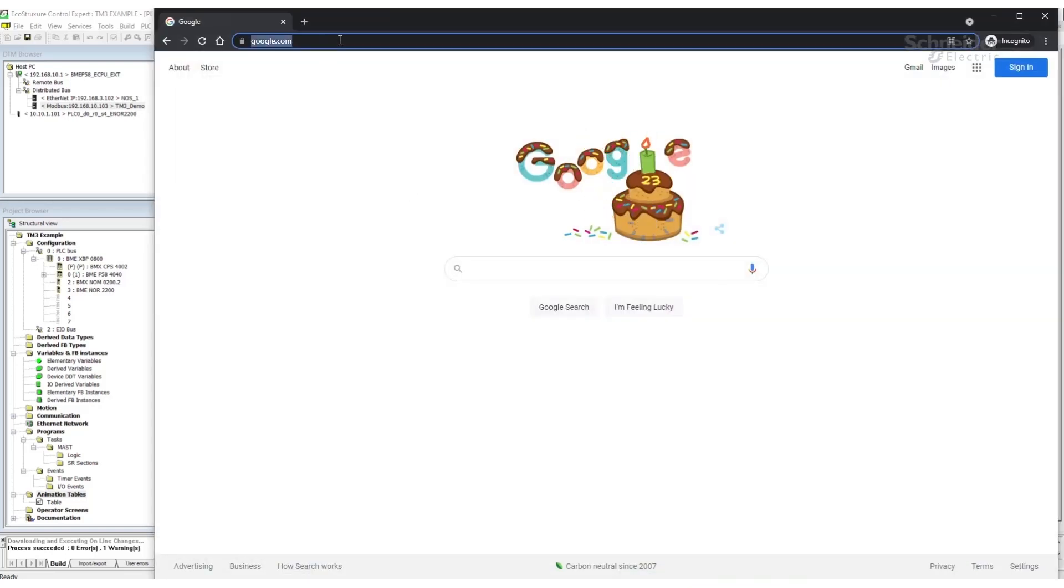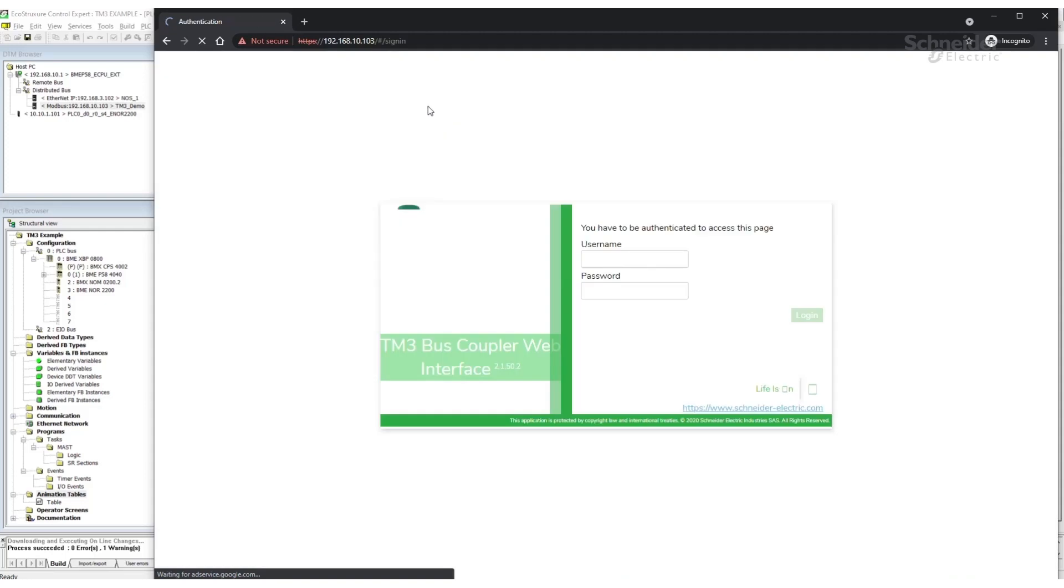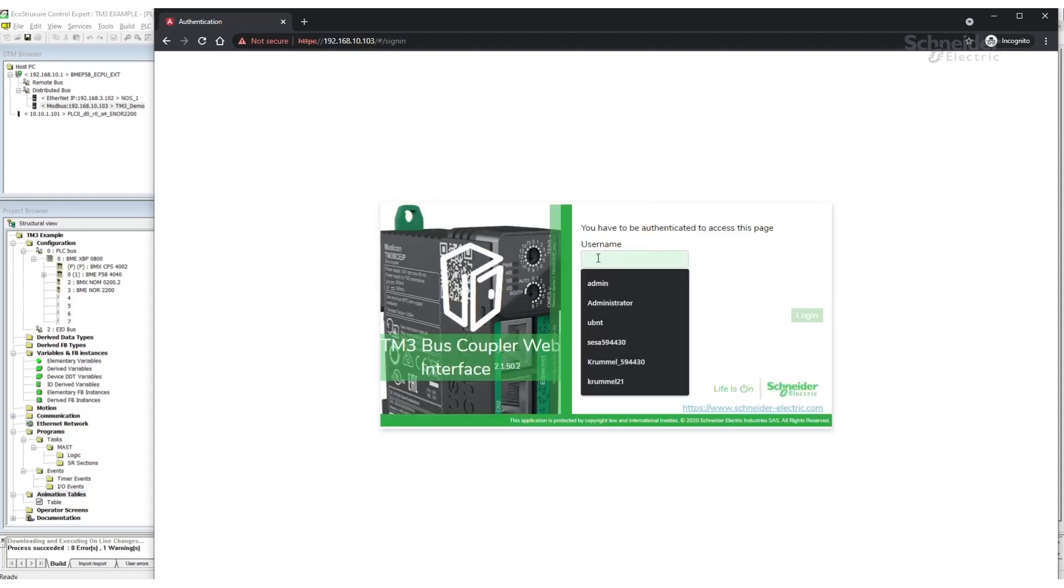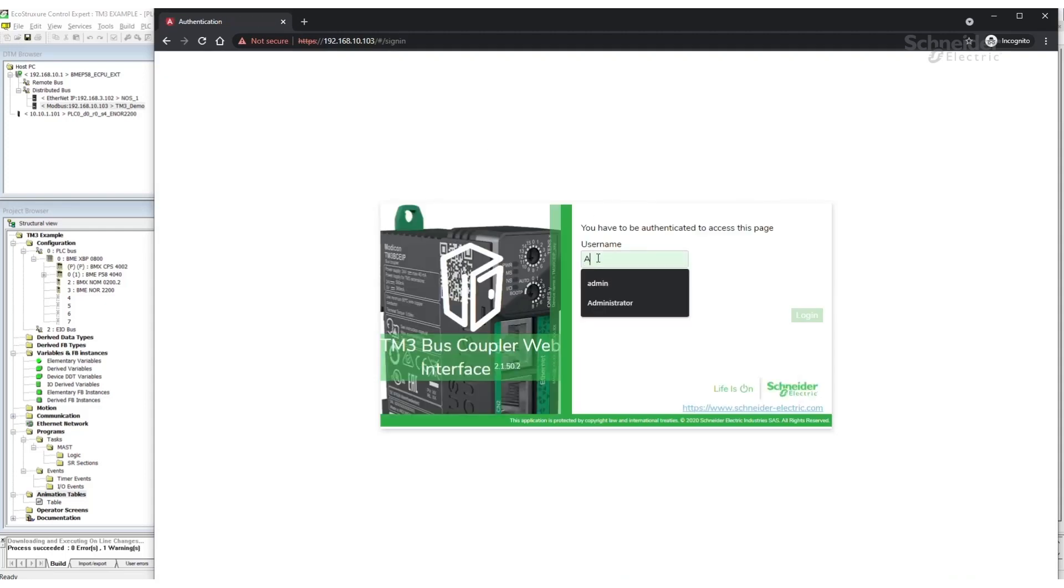Now that the project has downloaded successfully, we can power up the bus coupler. During the power up process, the bus coupler will get its IP address from the M580's DHCP server. Once it's powered up and connected, we can go to a web browser and verify the IP address was taken properly by going to the IP address assigned to it. Looking at the DTM browser, here's my IP address for the bus coupler. I'm going to type it in and go to that address. The default username and password is administrator for both. After the first login, it requires that the password be changed.